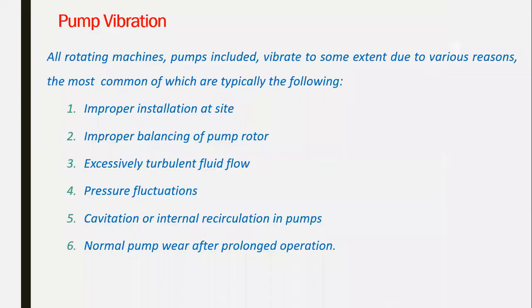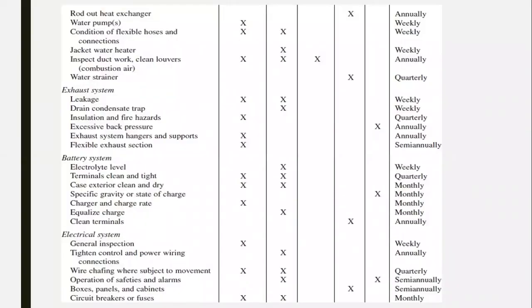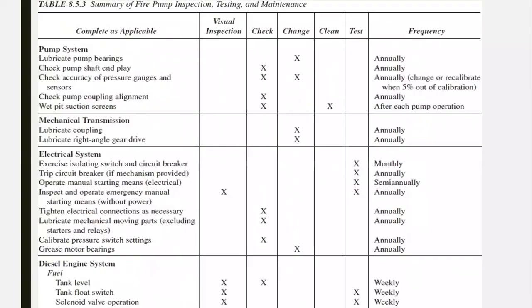So why am I showing you this here? Because this is a very important table and a very important part related to the exam. The exam will cover it for you. Battery, exhaust system, leakage: it has to be tested periodically, weekly, monthly, semi-annual, and annual, and it gives you a choice. So you have to know when it has to be checked weekly, tested, changed, inspected. And this table is available in the NFPA. It is table number 8.5.3.1, 8.5.3.